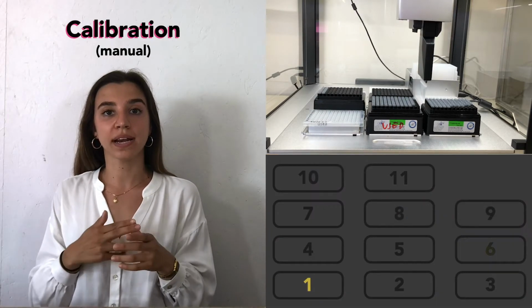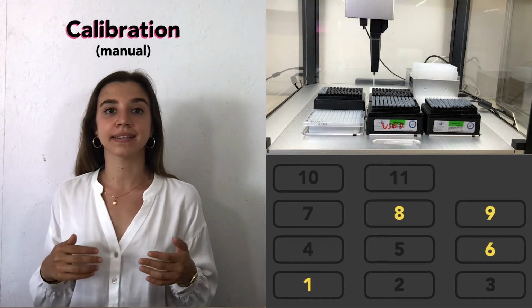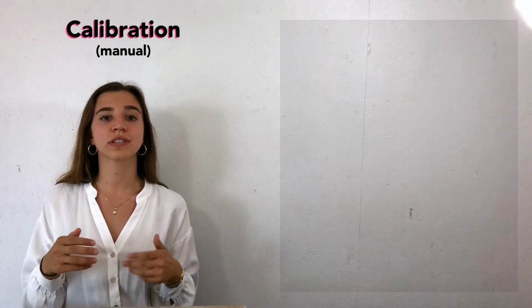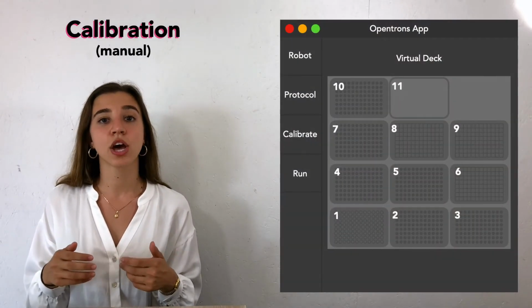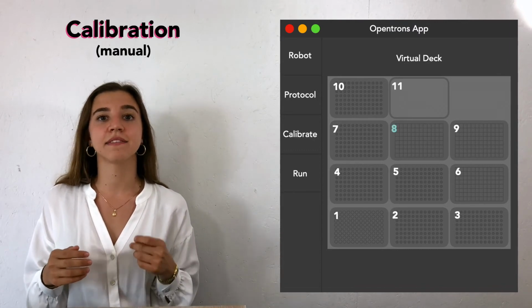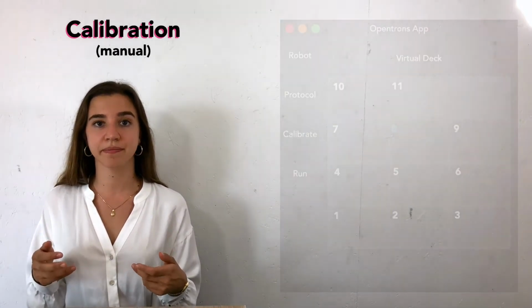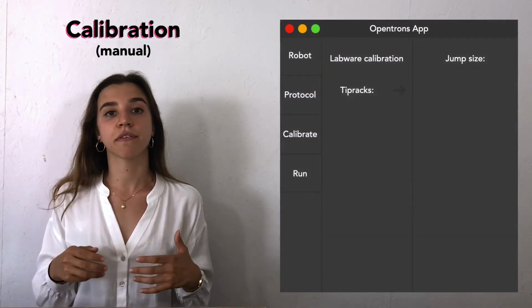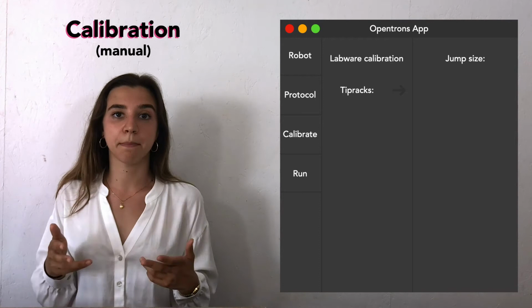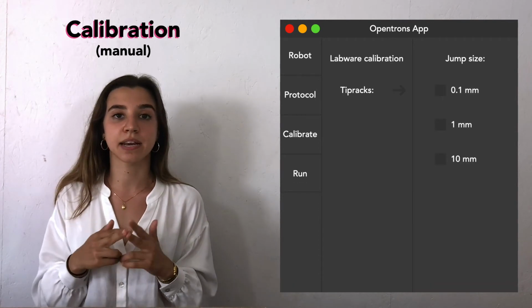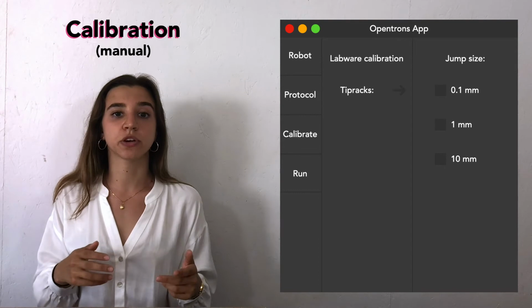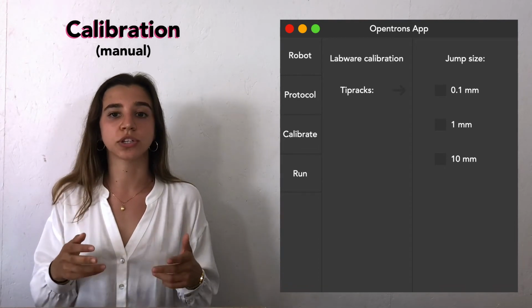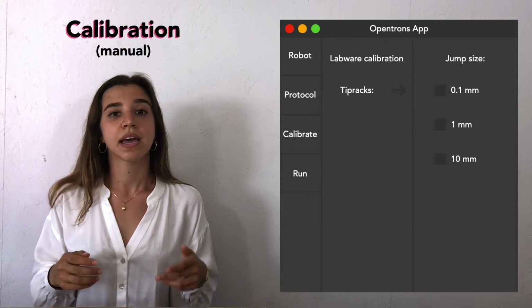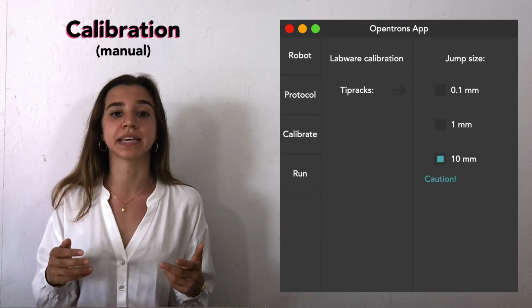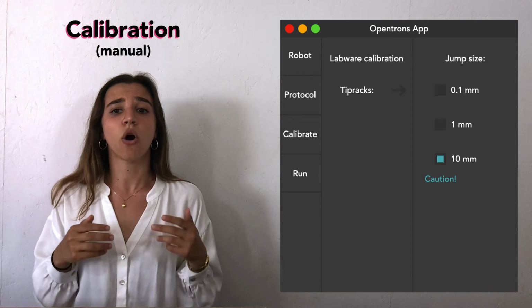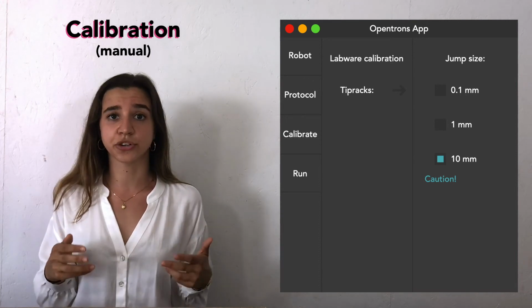This will be done for slots 1, 6, 9, and then 8 in that order. Do note that the OpenTrons app might prompt you to skip 8. Don't let this happen, and instead click the virtual slot to initiate calibration. When moving the pipette, you have the option of 3 different jump sizes from the OpenTrons app: 0.1, 1, and 10 millimeters. Now, especially when you're moving your pipette downwards, it is always better to be cautious with the distances being moved. If you use the 10 millimeter jump size too liberally, you can very easily end up crashing onto the deck. This means that you'll have to restart your calibration.